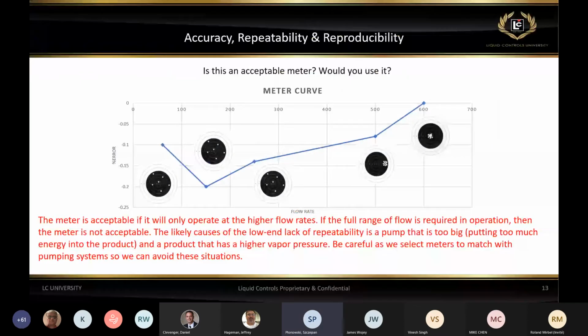And I think the last curve is fairly similar, but there are some significant differences. Again, is this meter acceptable? If you look at the overall spread of that meter on this curve, it's about 0.2%. So from an accuracy standpoint, it's not bad. But the first 2 points show to be accurate and also repeatable. But the last 3 points definitely are not repeatable, even though on average they are accurate. So is there anything wrong with this meter?